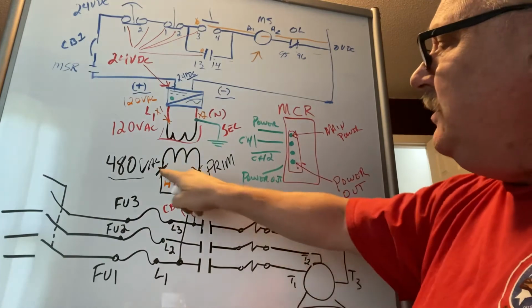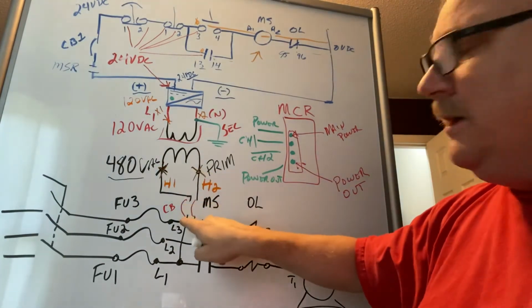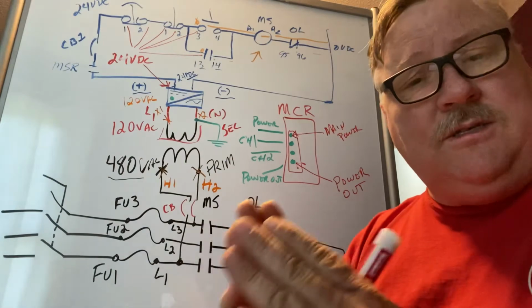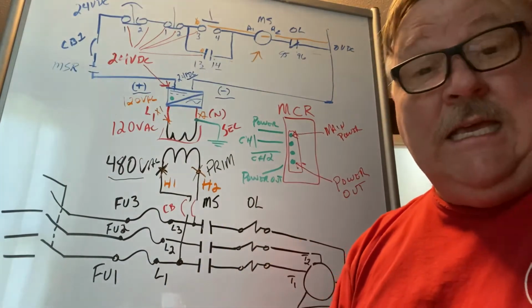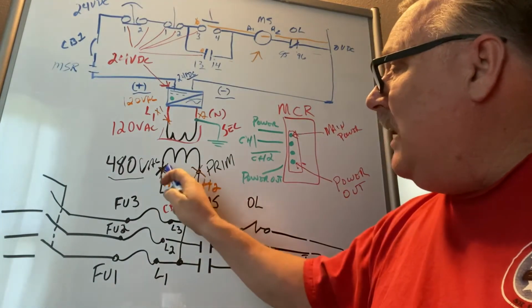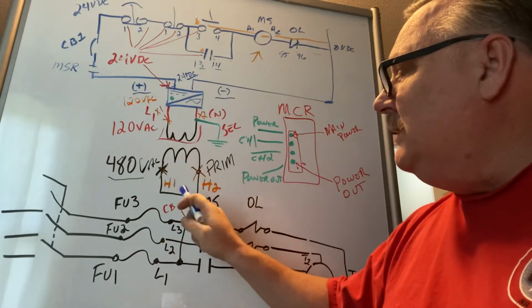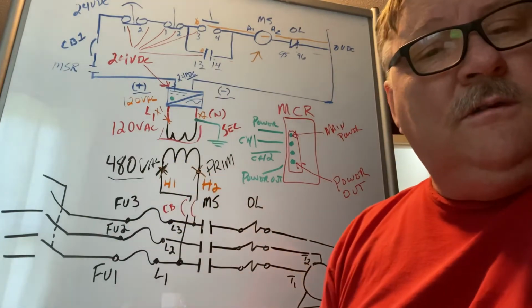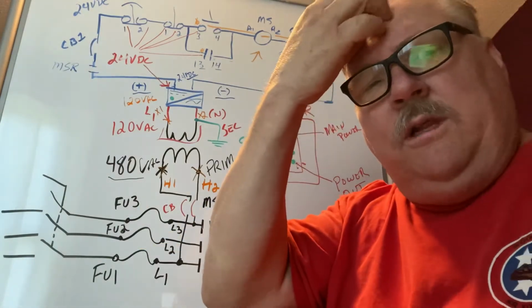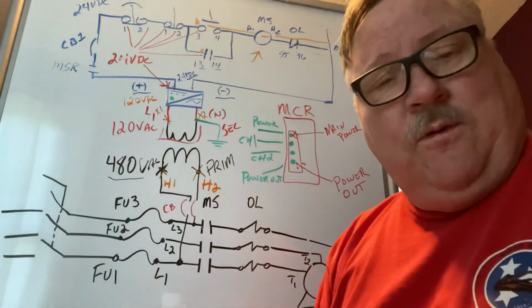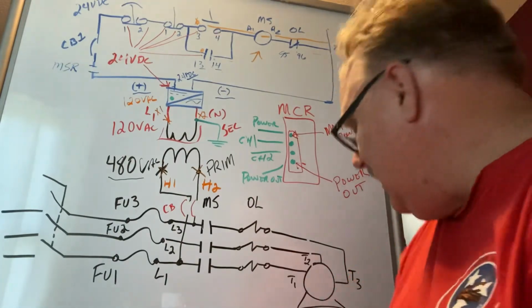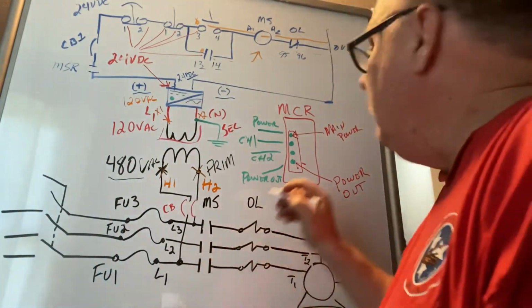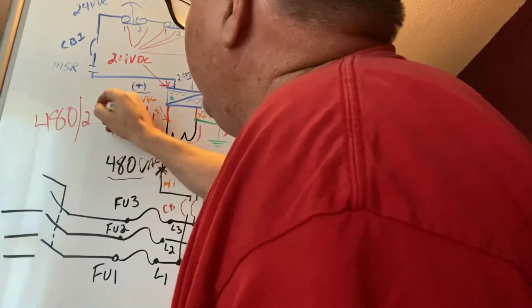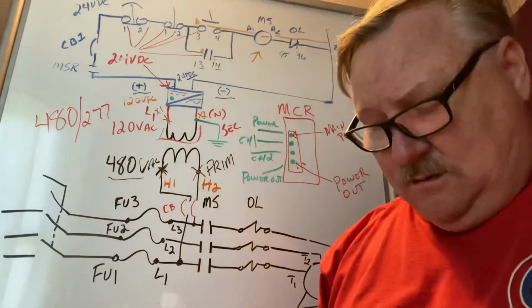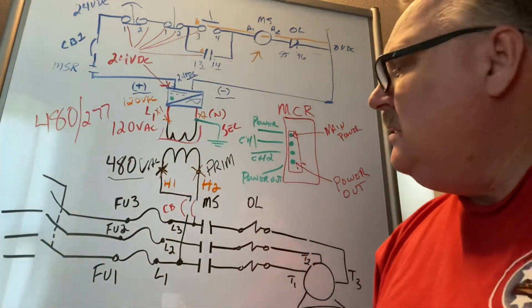So the next thing is, if you go to these and you don't get any power, check those circuit breakers. These circuit breakers should be interconnected, so if one trips, they both trip. If they don't, you will have power on both sides of this, but you'll only be reading your phase to ground, which will give you 277 if this is a 480 system. Okay, make sure everybody understands that 480 is a 277 on the phase to ground on your check.